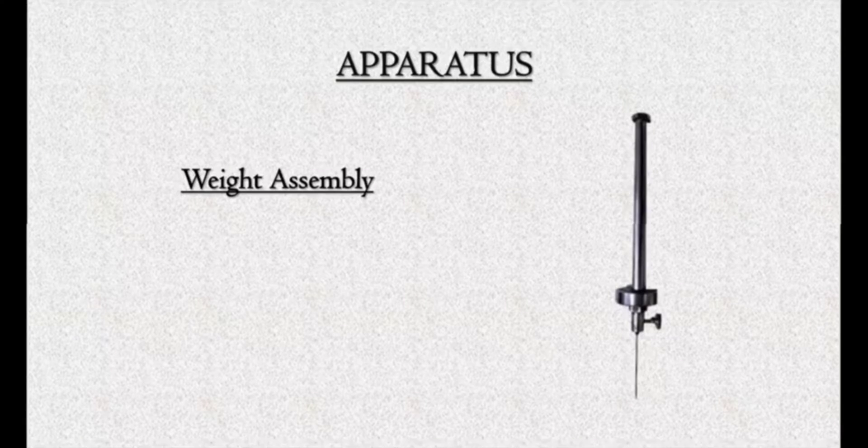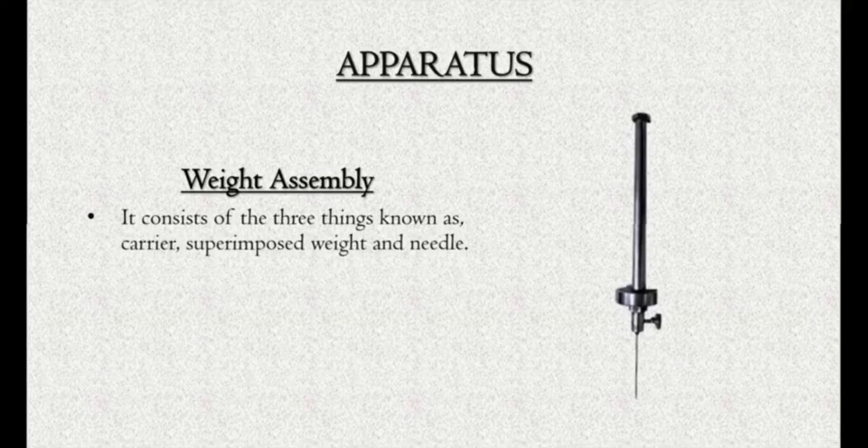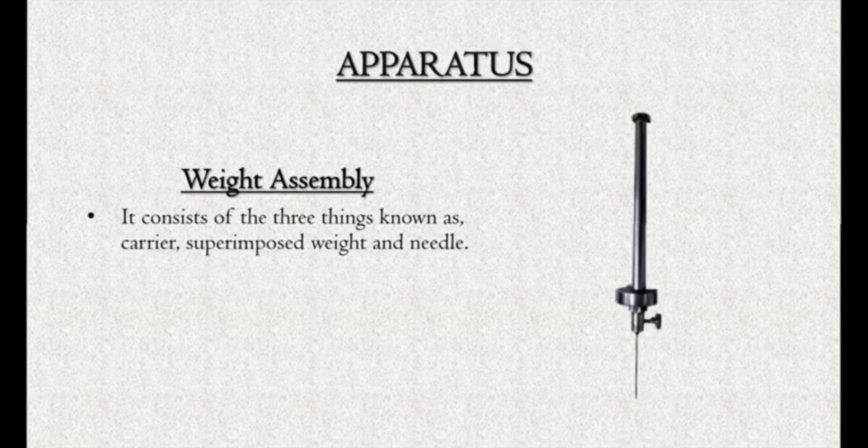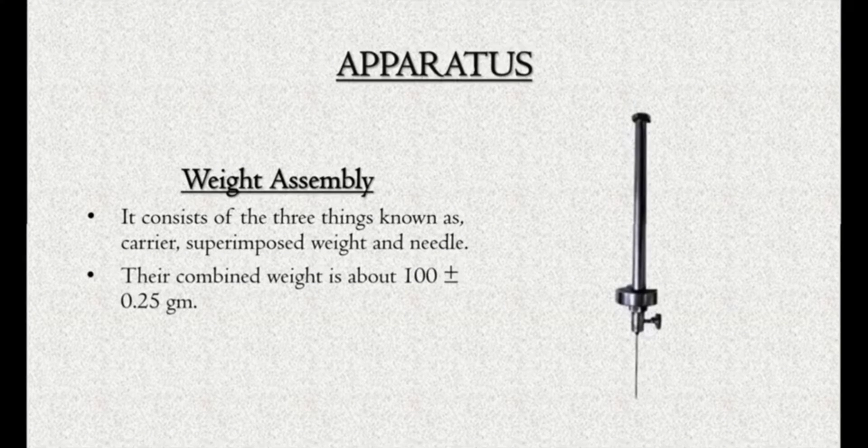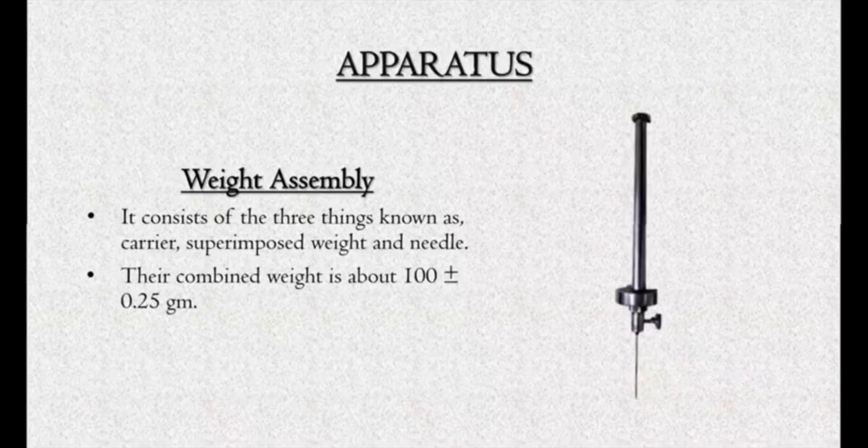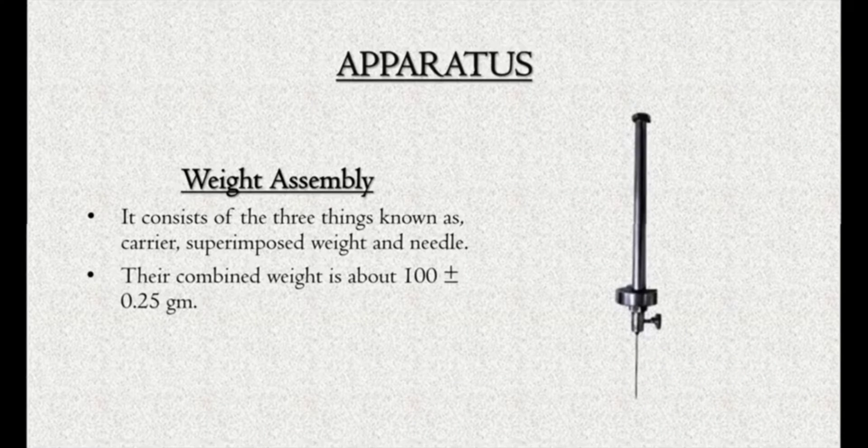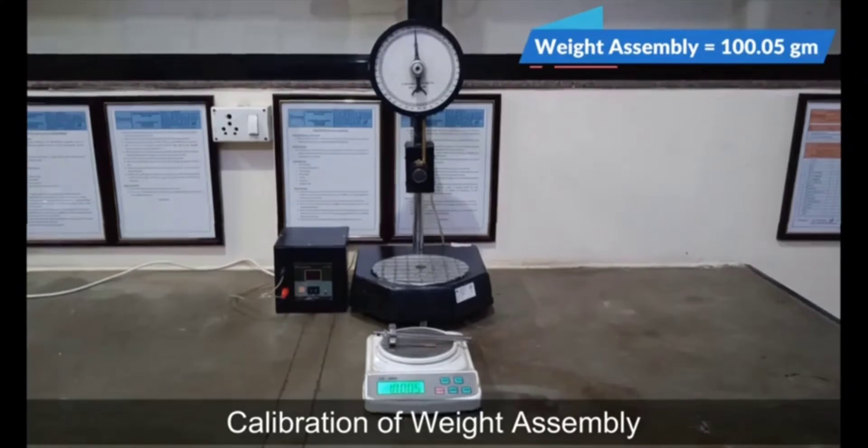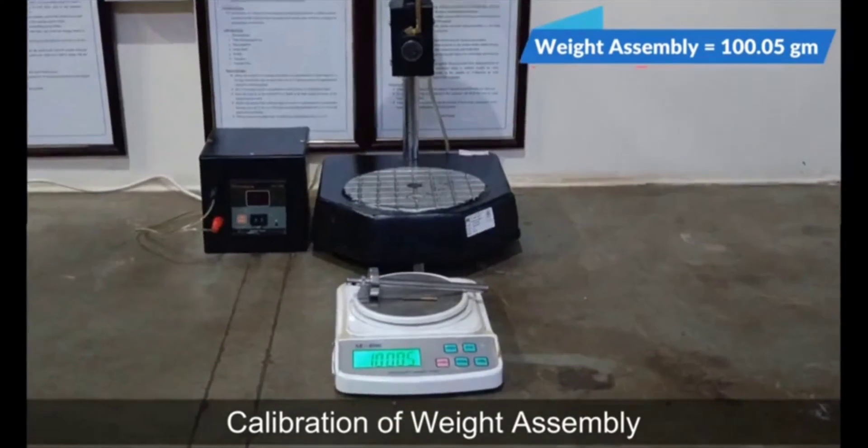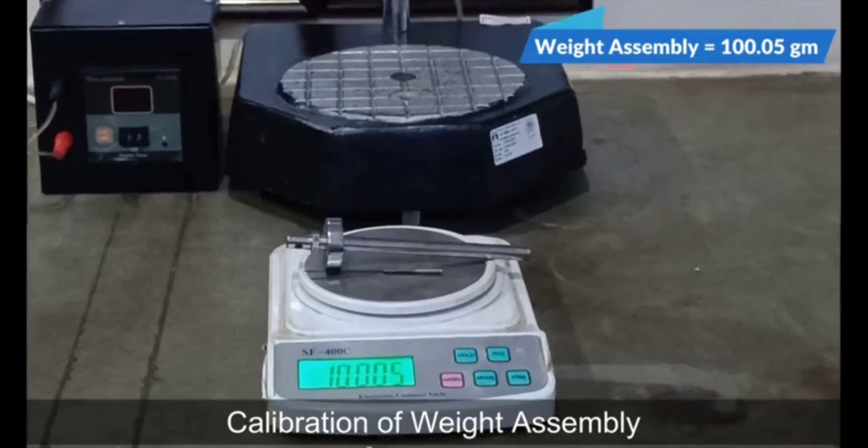Weight assembly: It consists of three things known as carrier, superimpose weight, and needle. Their combined weight is about 100 plus or minus 0.25 grams. Calibration of weight assembly: 100.05 grams.